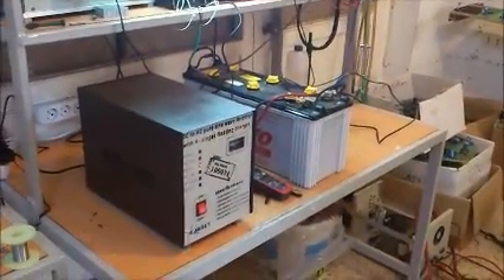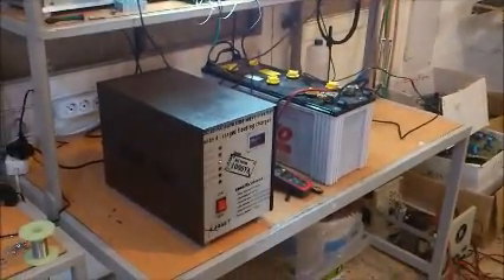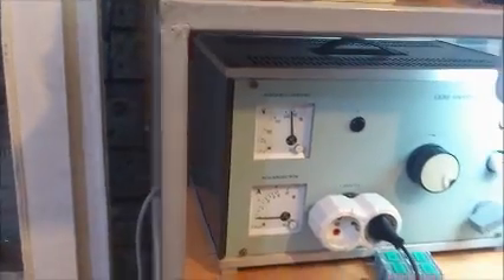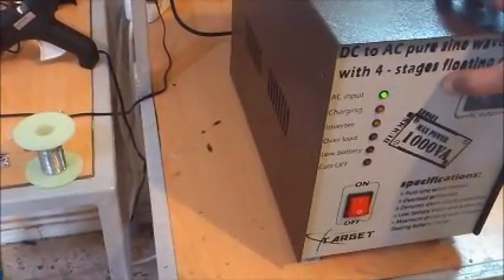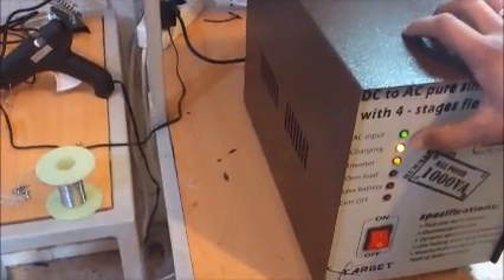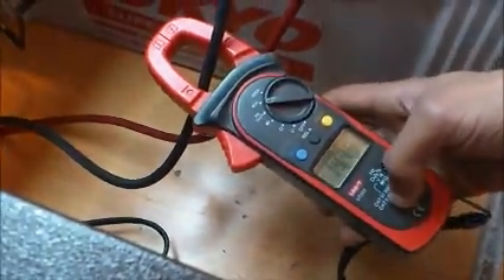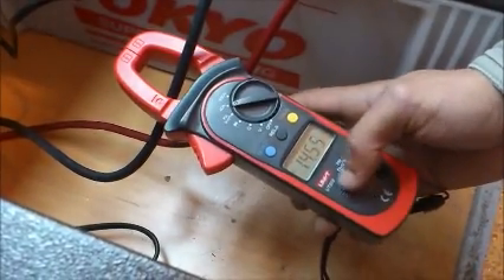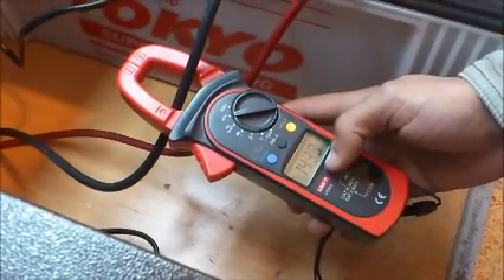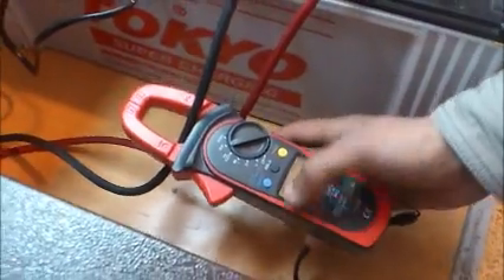Now we will talk about the charging, which is one of the specifications of this inverter. First we turn on the AC source, and wait until the inverter begins to charge the battery. Now we can see it when the lamp turns on. Using the DC clamp meter, we can see the current across the battery, which is around 15 amperes.